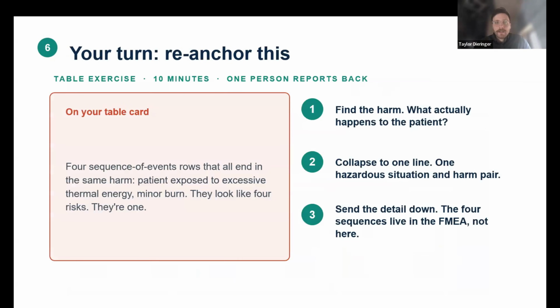Now we're going to do a little bit of an exercise here. Going back to that original example where we have a patient wearing our device and they're exposed to an excessive form of energy that results in a burn, we had those 4 risk line items attributed to that individual complaint. So the ask here is to identify the hazardous situation and harm pair that this complaint would be linked to. Let's collapse those 4 line items into one. Take a little time, think about the complaint coming in, and identify a hazardous situation harm pair applicable to that specific complaint. Share it in the chat, I'll give you a couple minutes and we'll see what comes through.